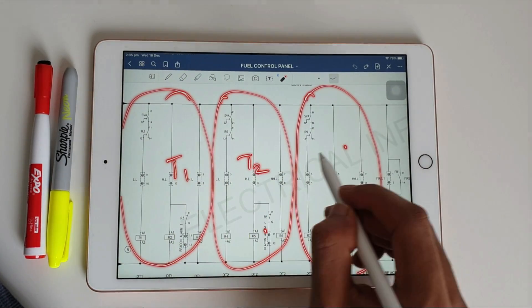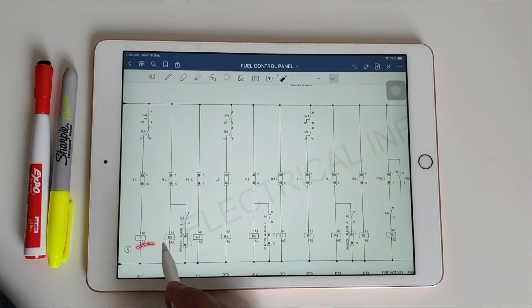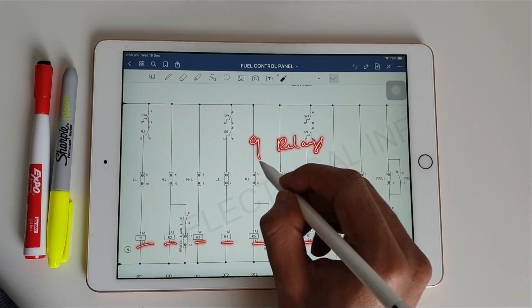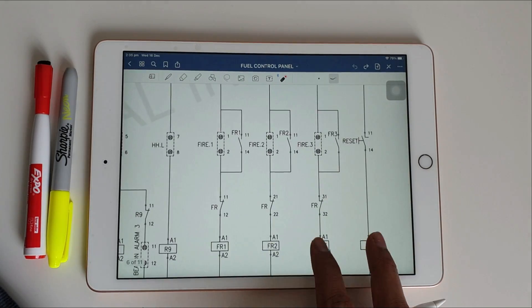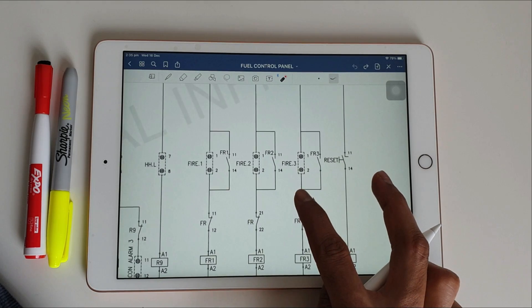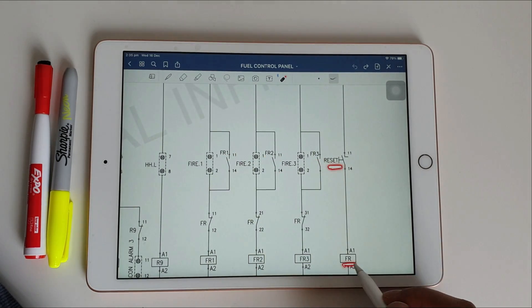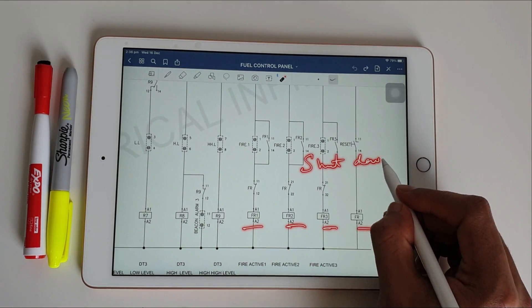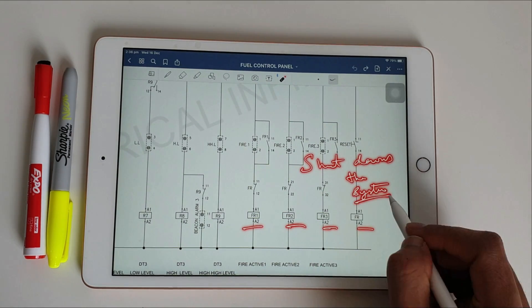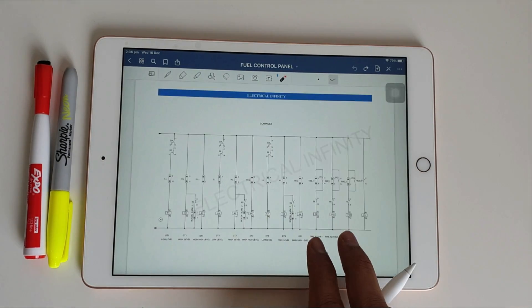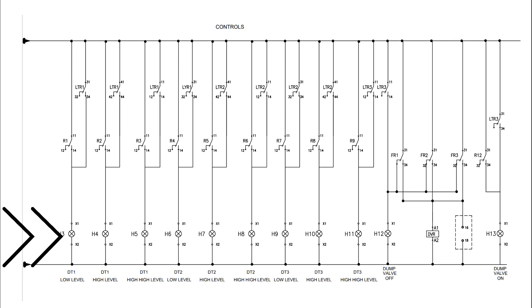Tank 1, tank 2, and tank 3 each use the same branch setup, so we have 9 relays in total for the auto setup. There is also a fire setup — when sensors detect fire, the FR fire relay turns on, which completely shuts down the plant after dumping the fuel from all tanks to the dump tank.